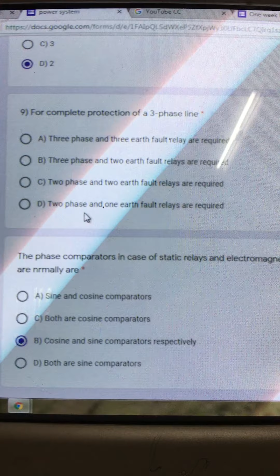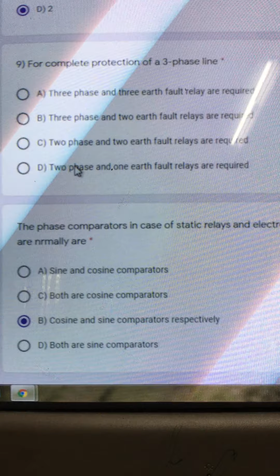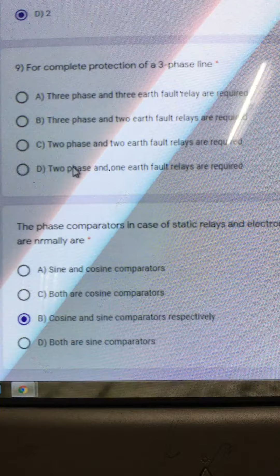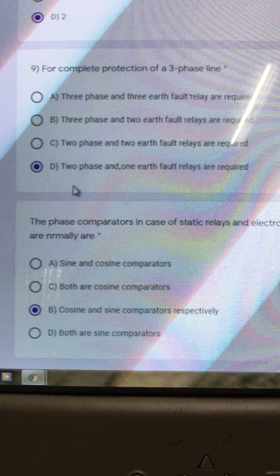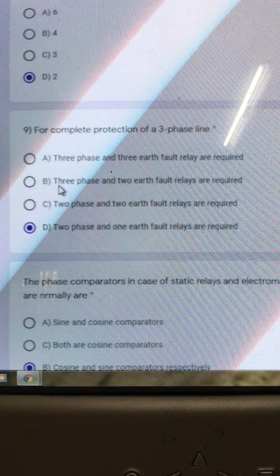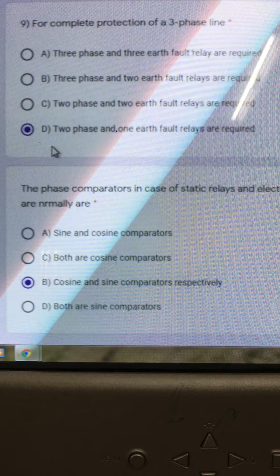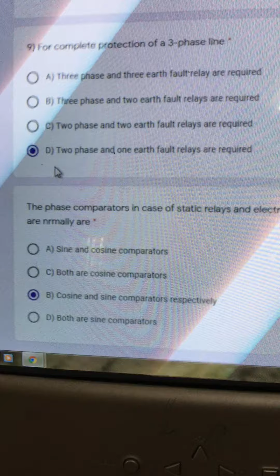For complete protection of a three-phase line: option A, 3-phase and 3 earth fault relays required; option B, 3-phase and 2 earth fault relays required; option C, 2-phase and 2 earth fault relays required; option D, 2-phase and 1 earth fault relay required. The correct option is option D, 2-phase and 1 earth fault relay required. The 2-phase relays are nothing but 2 overcurrent relays and 1 earth fault relay. For complete protection of a 3-phase transmission line, we require 2-phase and 1 earth fault relay.